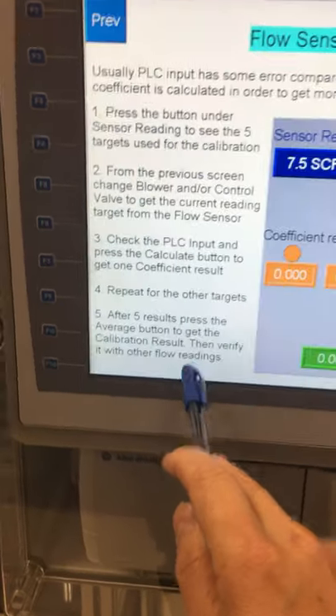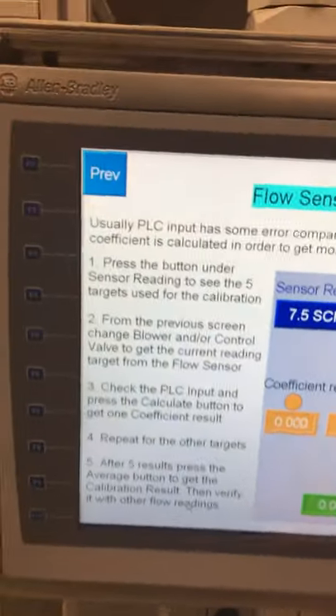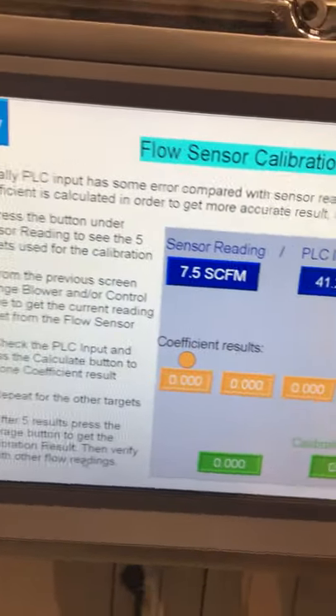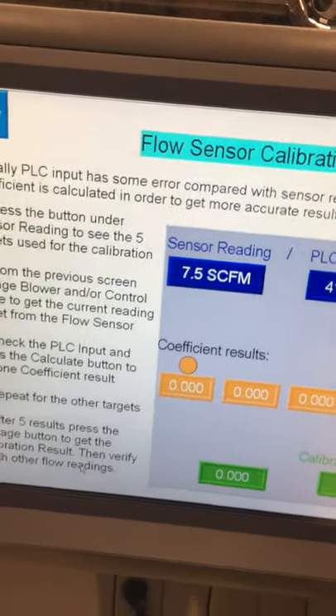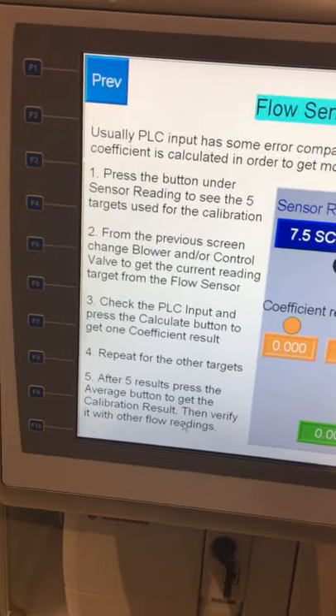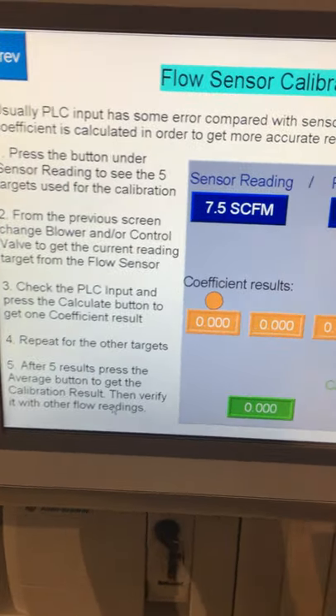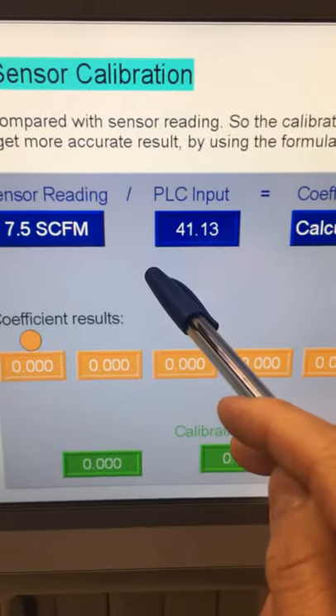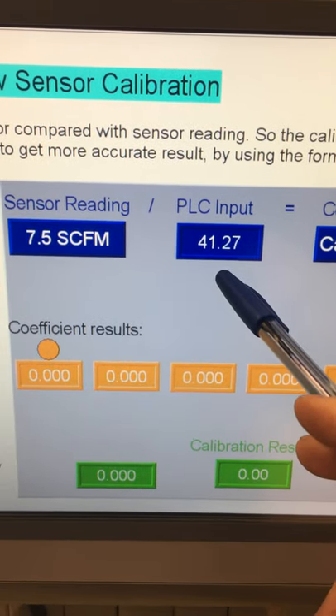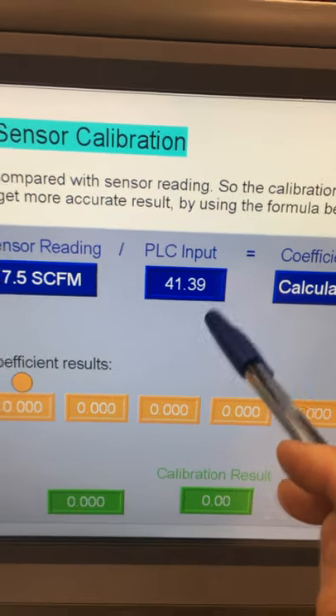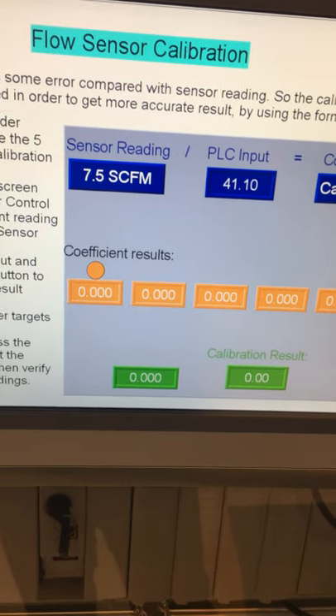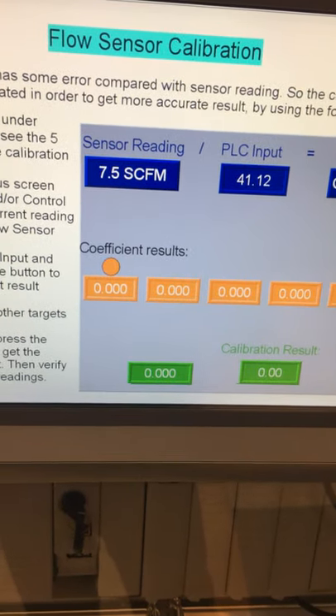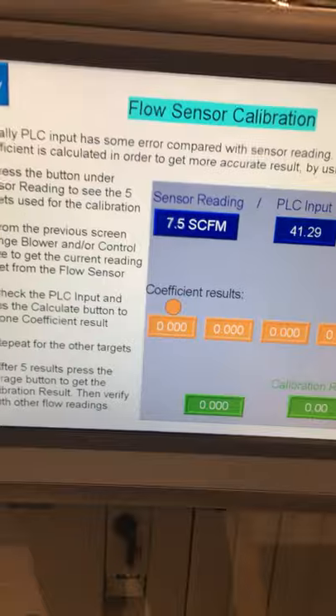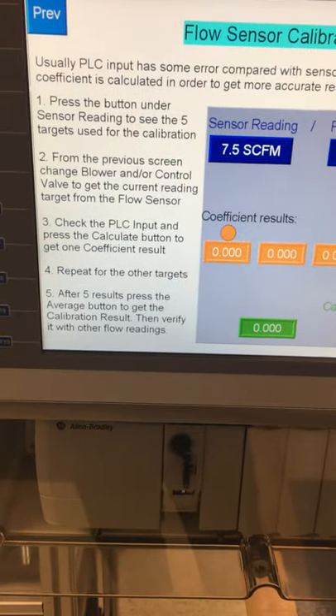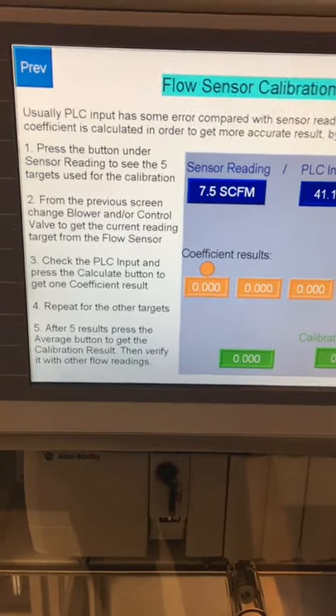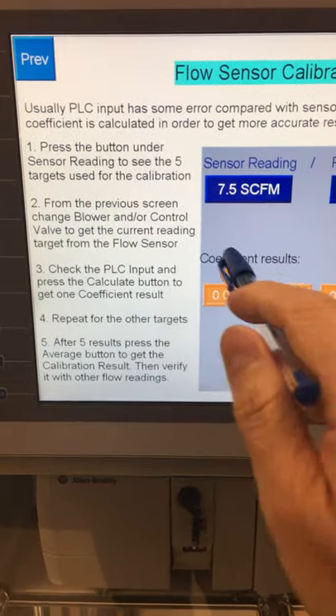So if you go to next. What we're going to do from here is calibrate the flow sensor, right? The flow sensor has the analog input to the PLC. You can see right now the PLC reading is 41 something, right? This reading needs to be calibrated because it doesn't exactly match up with the real reading. So how do we do the calibration? This is the process.